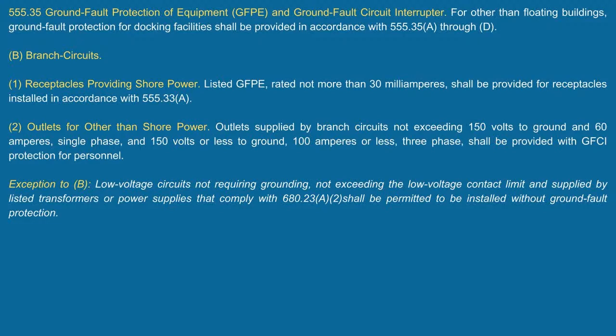No, it doesn't. And then it talks about outlets for other than shore power. And it says outlets supplied by branch circuits not exceeding 150 volts to ground and 60 ampere single phase, and 150 volts or less to ground, 100 amperes or less three phase, shall be provided with GFCI protection for personnel. Okay. Now, that is where you're going to be setting up, just like I do for shore power. These are going to be cord and plug connected type devices. This is not going to be something that's hardwired. And that's where the problem starts coming in.